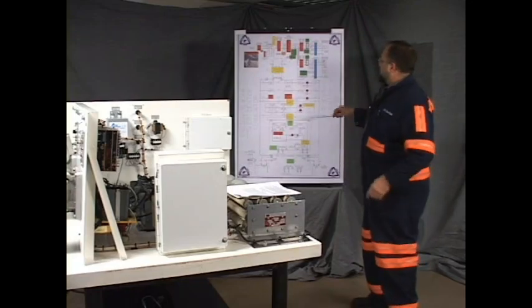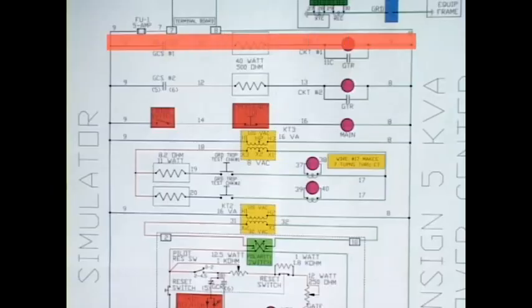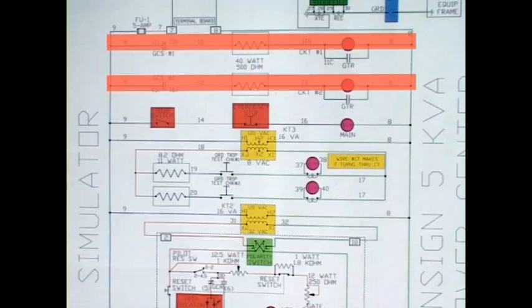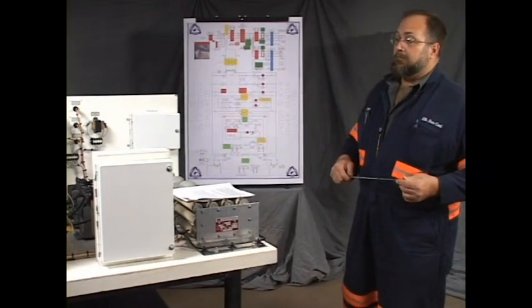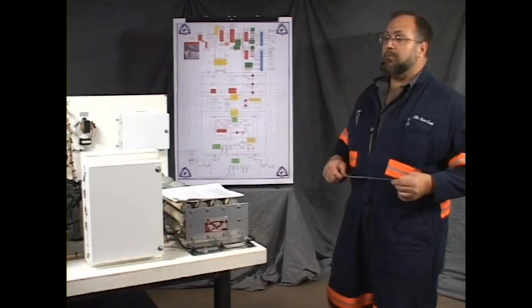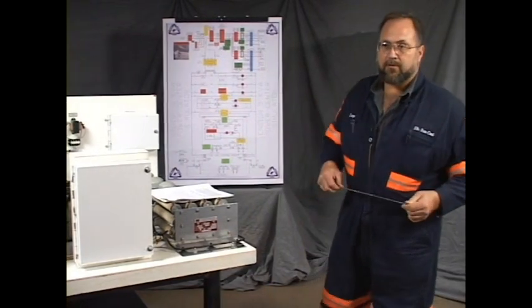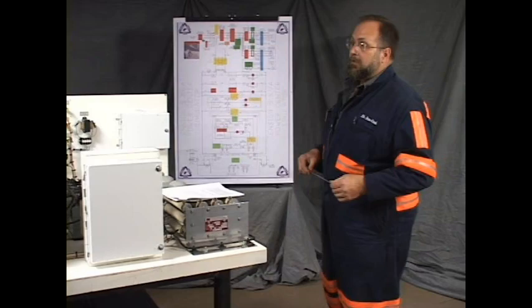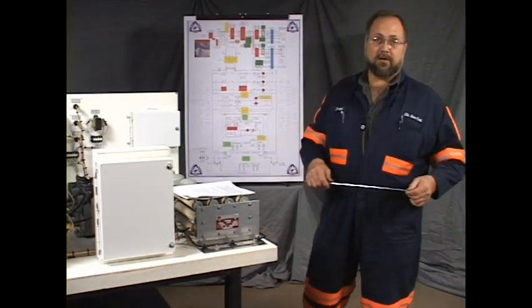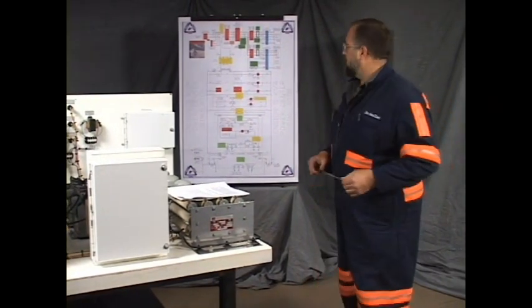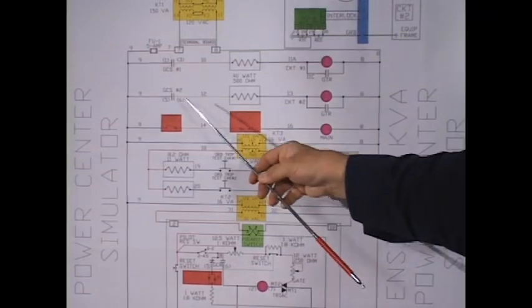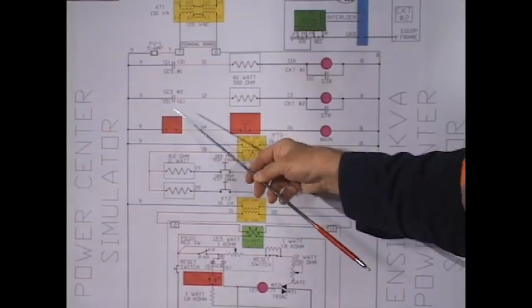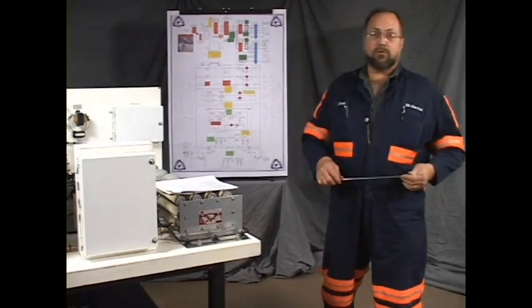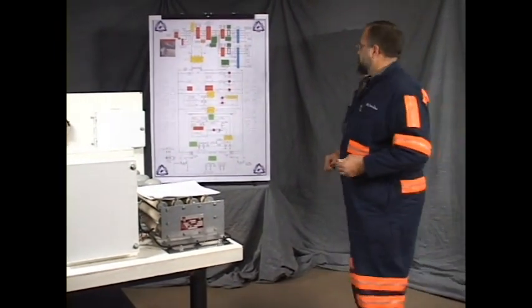We have two circuits that you'll be troubleshooting. One for circuit number 1 and one for circuit number 2. And although they are individual, they're powered from the same source, and they're identical with the exception of the ground monitoring used. The ground monitoring on circuit 1 is an impedance type ground monitor. The ground monitor in circuit number 2 is a tone type or audio ground monitor. The contacts, for all practical purposes, are the same. It's just the different device to close those contacts that is the only difference.